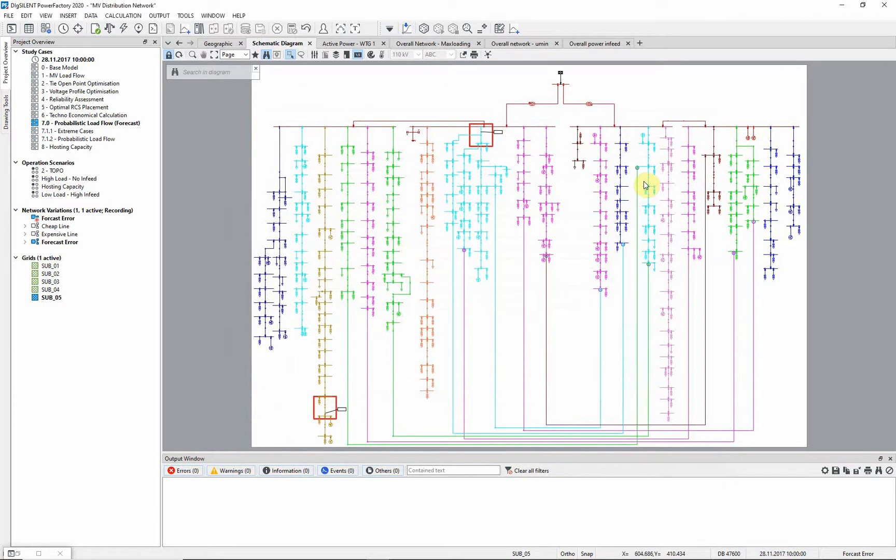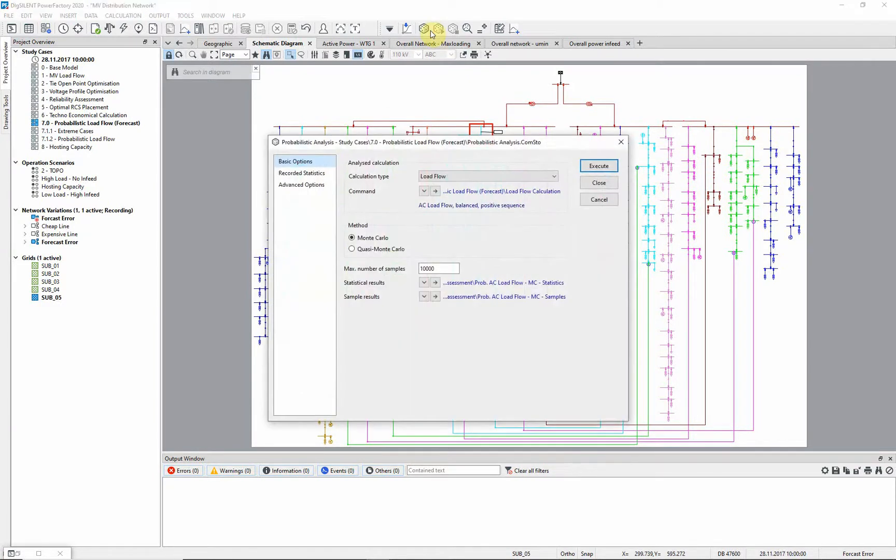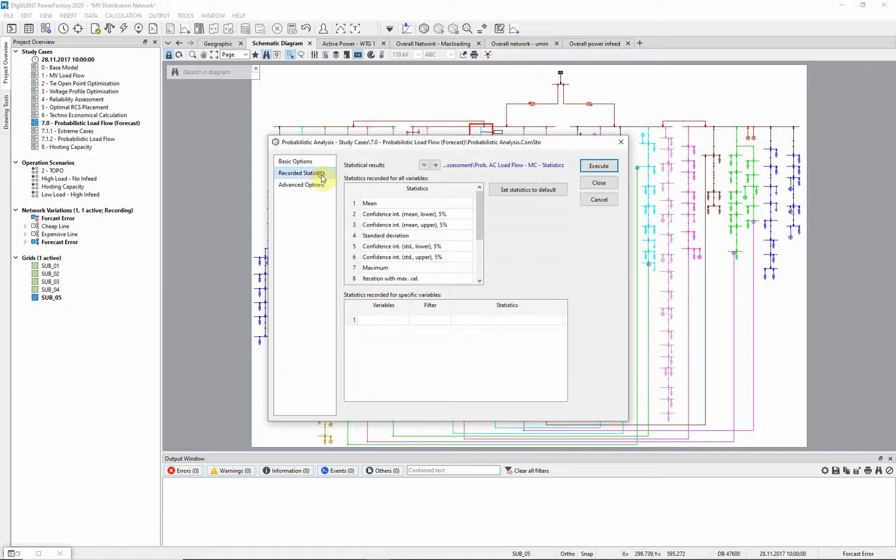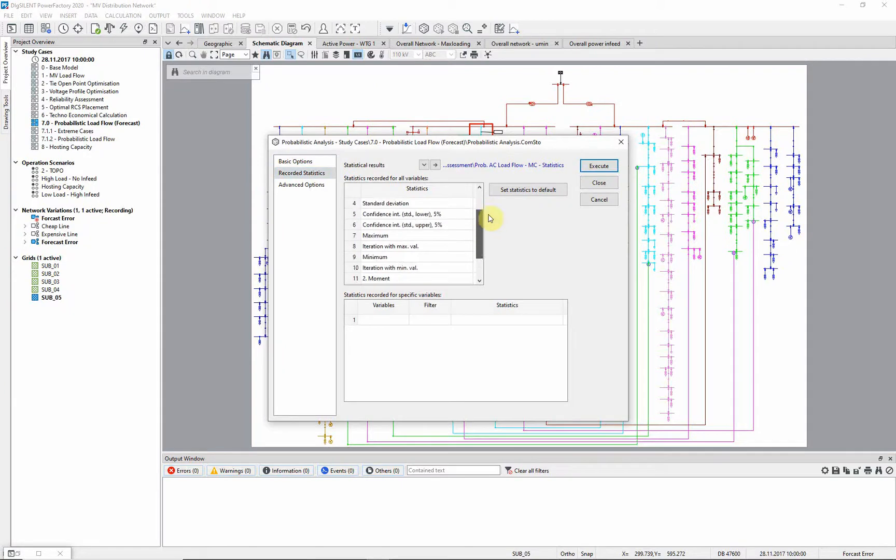We can now run the probabilistic analysis. The command is accessible via the probabilistic analysis tool box. We will analyze the load flow probabilistically. For this, we will use the Monte Carlo method with 10,000 samples. On the recorded statistics page, we can define which statistics are to be recorded for the selected variables. We are now ready to execute the command.